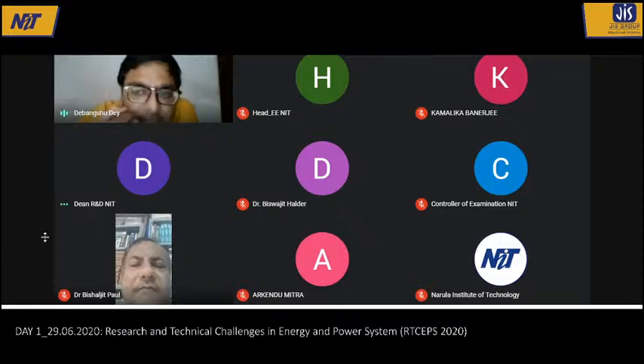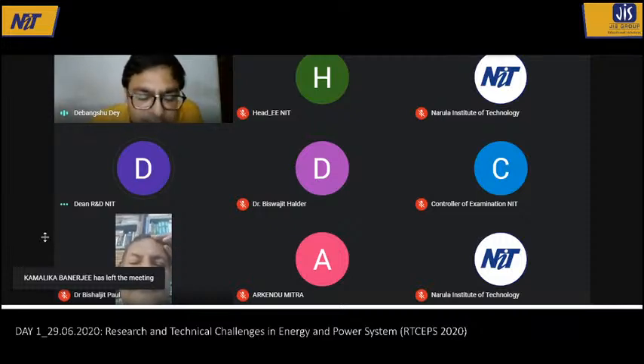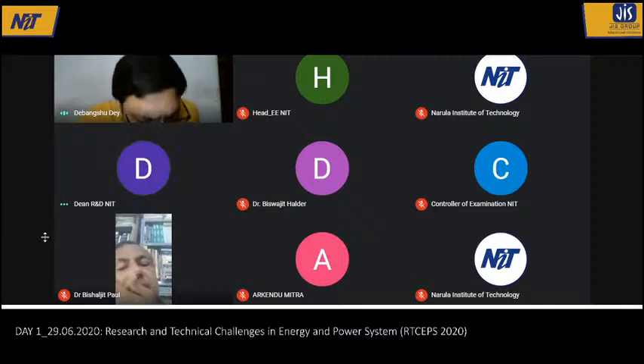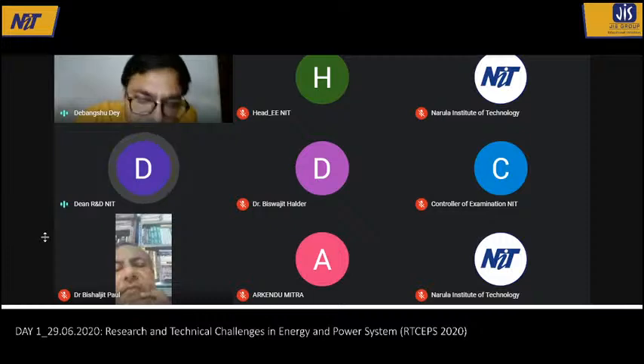Actually sir, the purpose of doing these two tests are different. If we are trying to find out the overall insulation condition, that is, if a transformer is working on the normal power frequency voltage and we want to know the insulation condition, then we should go for PDC. We apply the step voltage and then record the discharge current for that voltage. That is one purpose. Another thing is, if we are trying to find out the impulse withstand capability of the transformer insulation, then we should go for the impulse test. So these two tests have their own advantages and requirements; one cannot replace the other. It depends on the rating of the power transformers.